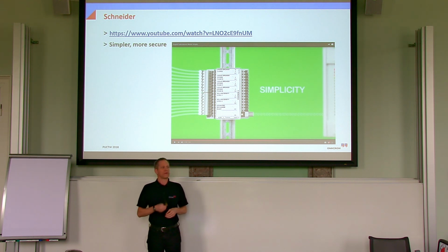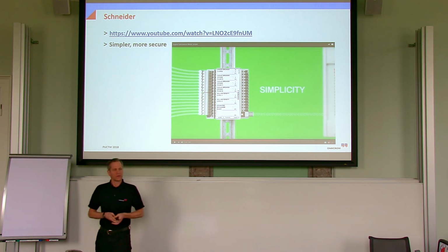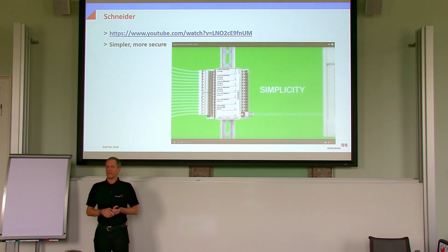And of course, they do refurbishment on a regular schedule. And at that time, this person told me how many loose contacts or, let's say, open wire loops that do not transfer information when they should, they detected when they refurbished the substation. It was a decent number, we thought. They were doing a good job in their maintenance, but you find things like that.